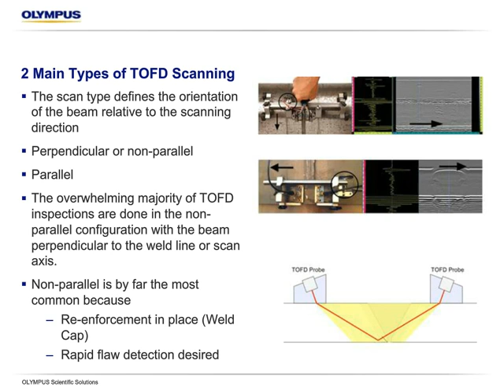So, application summary. There are a lot of applications of TOF, but by far the two biggest ones are one for weld and flaw detection, and one for corrosion and erosion. When we look at weld inspections, we're usually doing one of two things. I'd say about 80% or better is for volumetric flaws within the weld, and then a little bit on sizing and monitoring, as a complementary technique. If we know a flaw is there, we want to watch it to see if it grows before we have to make the call to shut that down when it becomes a critical length or height. And the other one being corrosion. On the display, you can see the differences here as well.